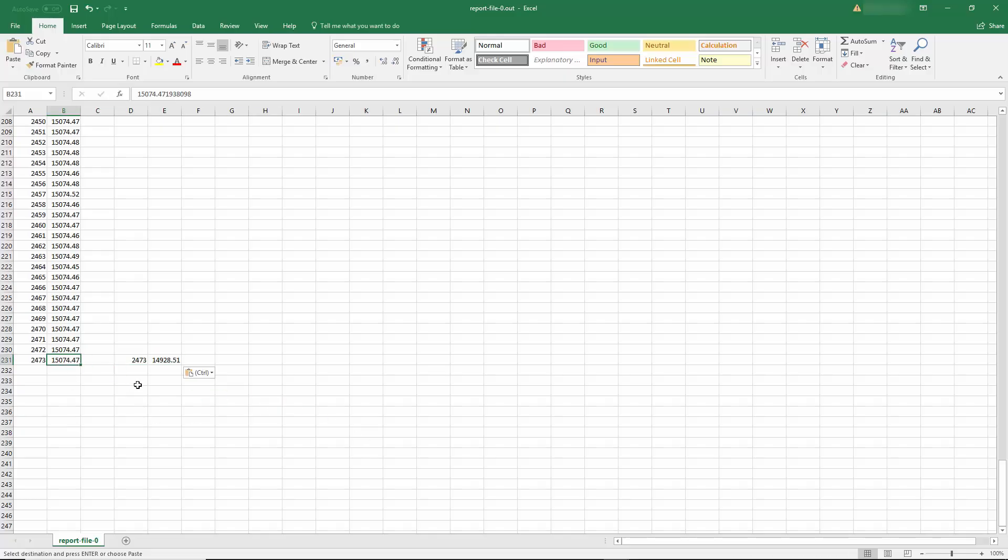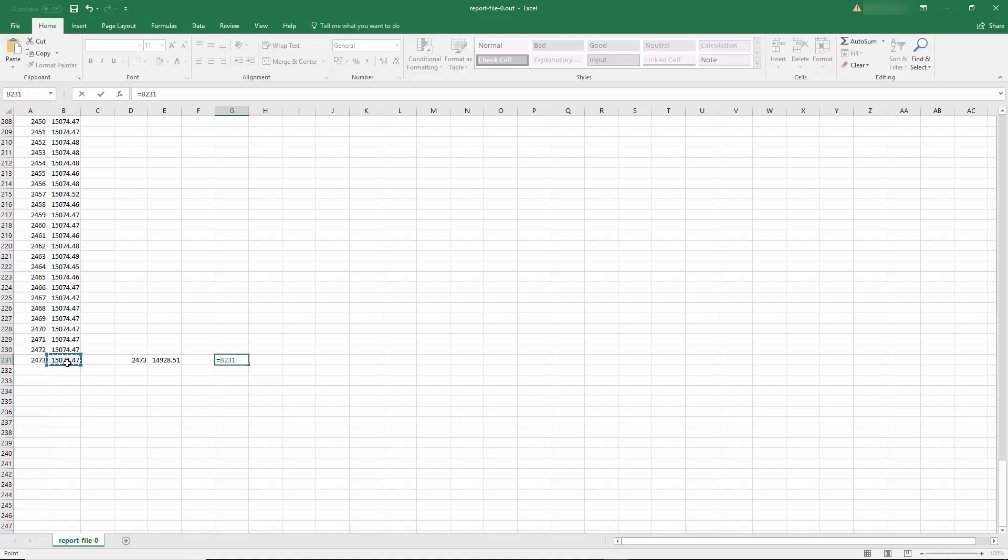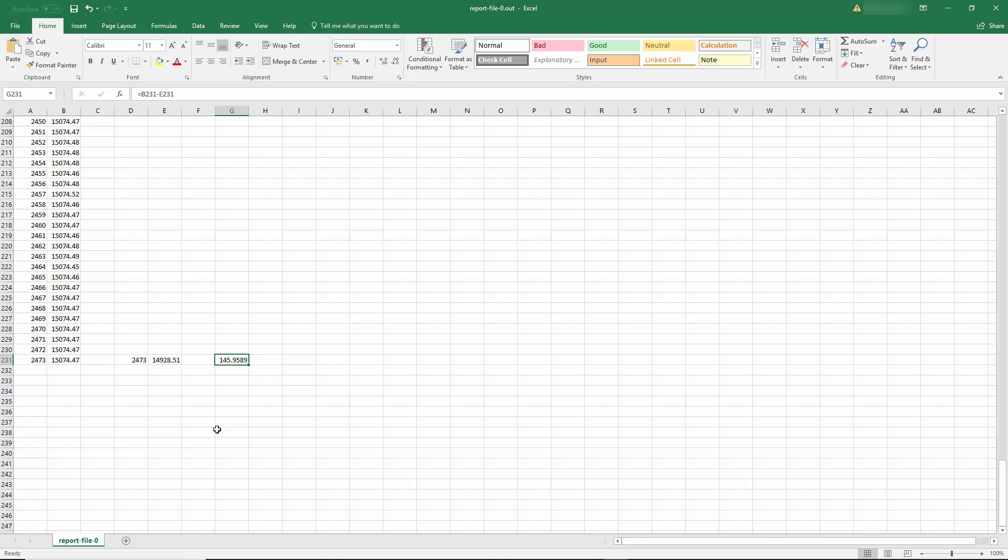So you can see now at this time step, which is 2473, we have at the upstream side of the valve, a pressure of 15,074 Pascal and the downstream side of the valve, we have 14,928 Pascal. If we subtract the two, we get a delta p of 145.9 Pascal.